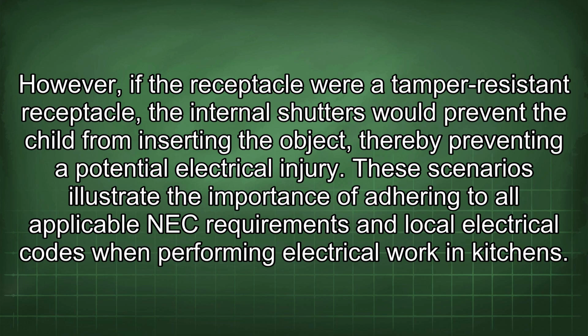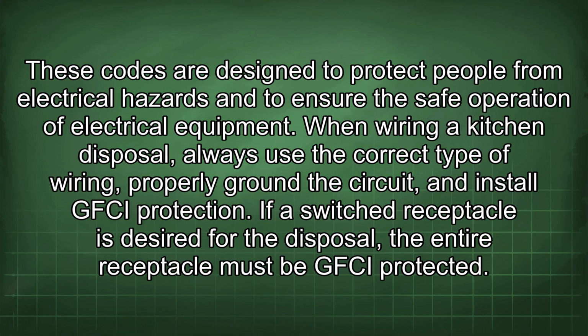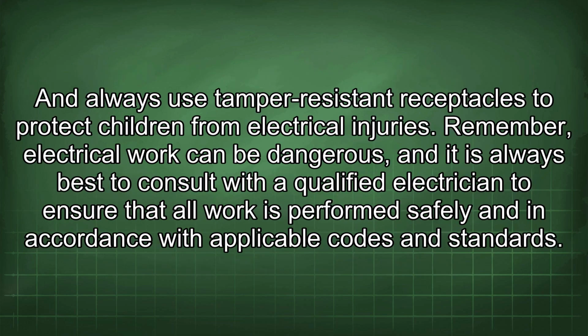These scenarios illustrate the importance of adhering to all applicable NEC requirements and local electrical codes when performing electrical work in kitchens. These codes are designed to protect people from electrical hazards and to ensure the safe operation of electrical equipment. When wiring a kitchen disposal, always use the correct type of wiring, properly ground the circuit, and install GFCI protection. If a switched receptacle is desired for the disposal, the entire receptacle must be GFCI protected. And always use tamper-resistant receptacles to protect children from electrical injuries.